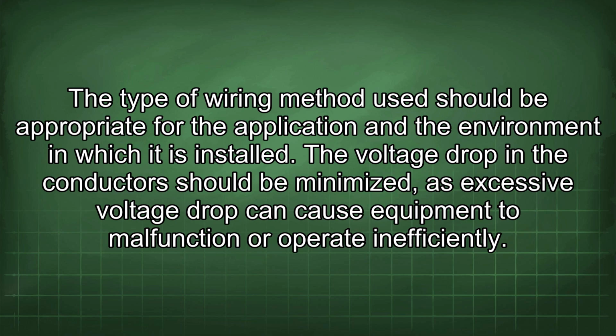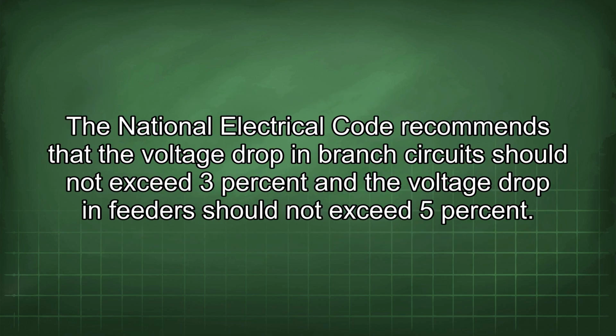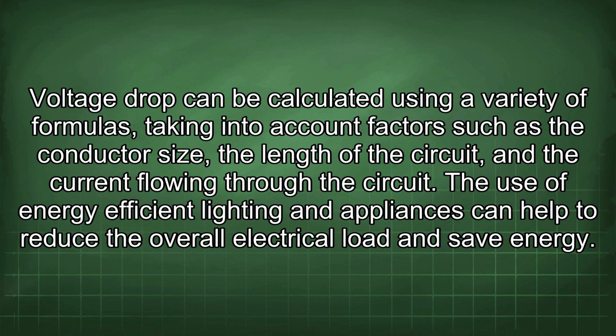The voltage drop in the conductors should be minimized, as excessive voltage drop can cause equipment to malfunction or operate inefficiently. The National Electrical Code recommends that the voltage drop in branch circuits should not exceed 3% and the voltage drop in feeders should not exceed 5%. Voltage drop can be calculated using a variety of formulas, taking into account factors such as the conductor size, the length of the circuit, and the current flowing through the circuit.